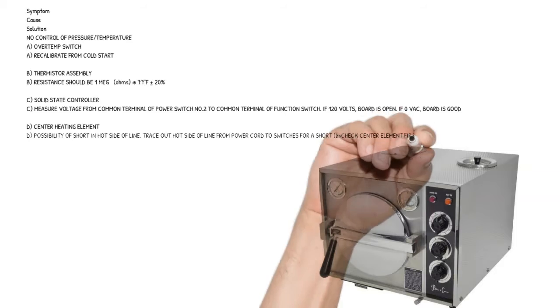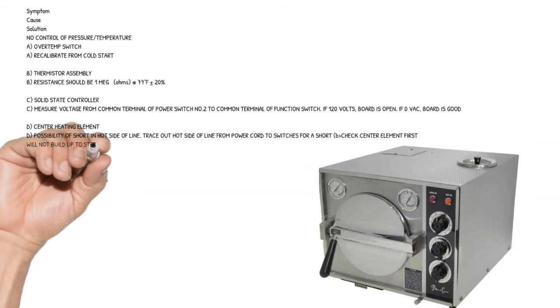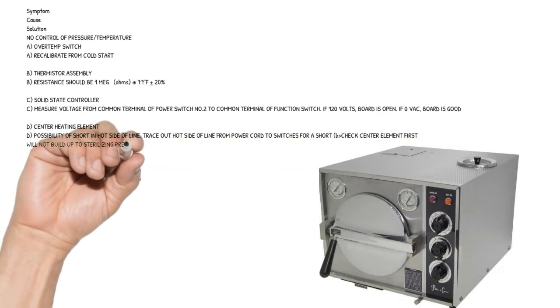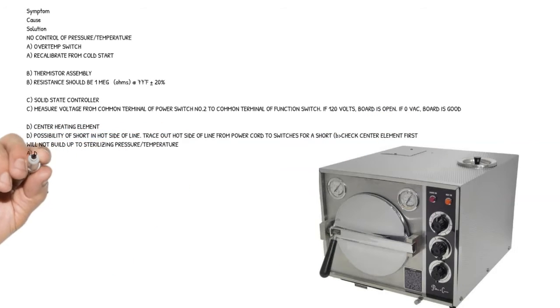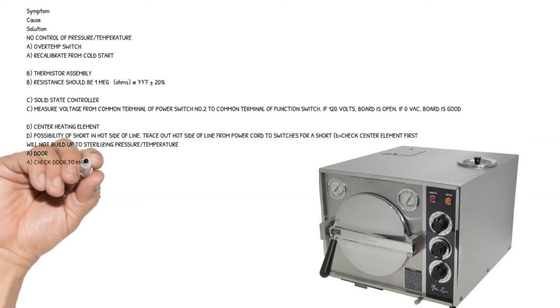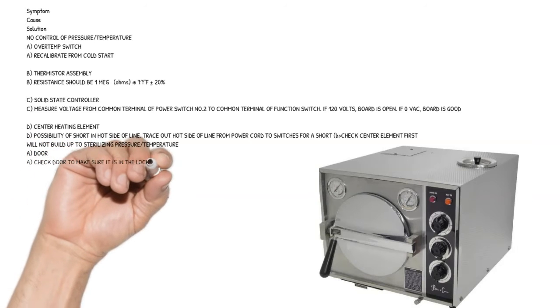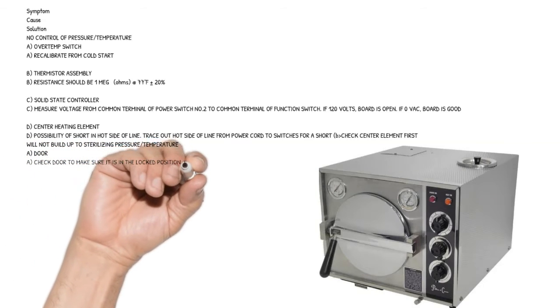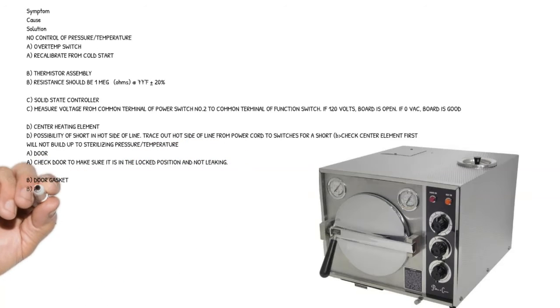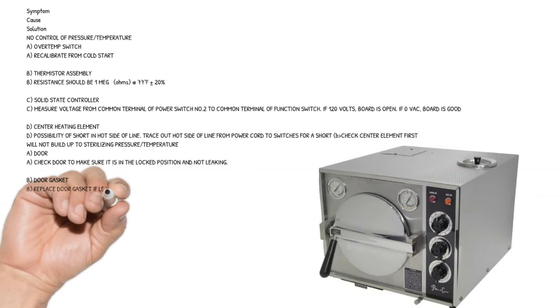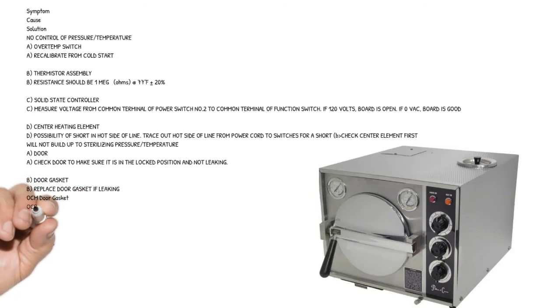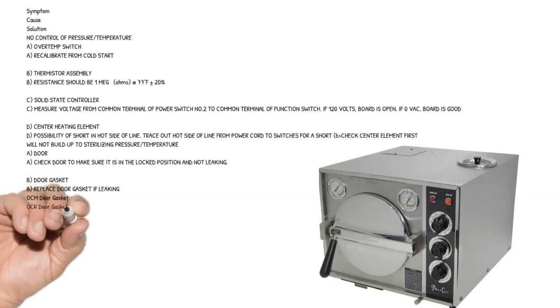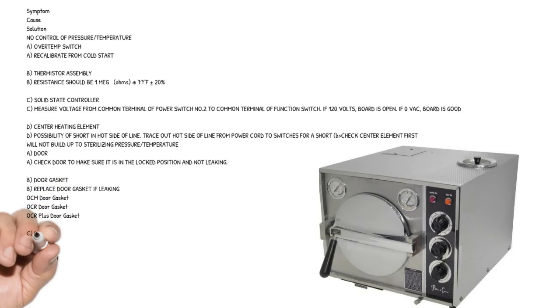Symptom: Will not build up to sterilizing pressure or temperature. Cause A: door - check door to make sure it is in the locked position and not leaking. Cause B: door gasket - replace door gasket if leaking. OCM door gasket, OCR door gasket, OCR plus door gasket.